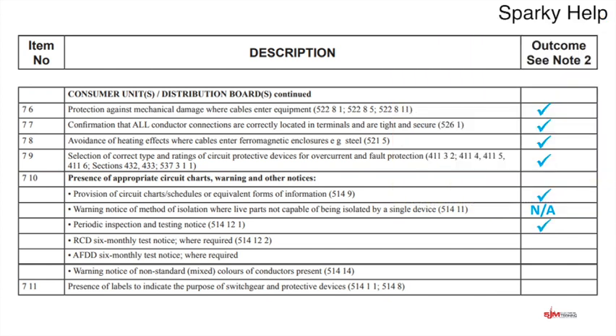Periodic inspection notice, does exactly what it says on the tin, whenever the next inspection will be. Remember, it is the designer who decides, on an initial verification, when the next inspection will be carried out. RCD 6 monthly test, and you can also lump in with that arc fault detection 6 monthly test, because there are devices out there that are RCBO and also arc fault detection. They're still quite pricey, but they are out there, so you potentially have one test button to do both of those, but luckily they're both 6 months.